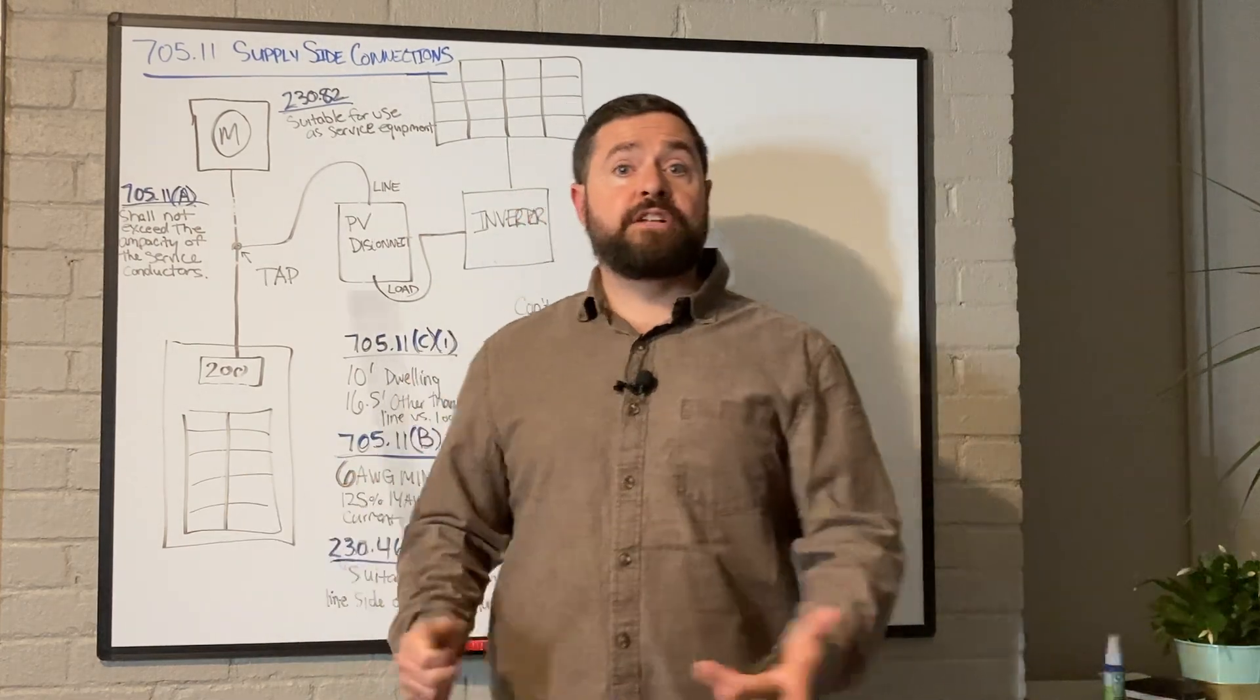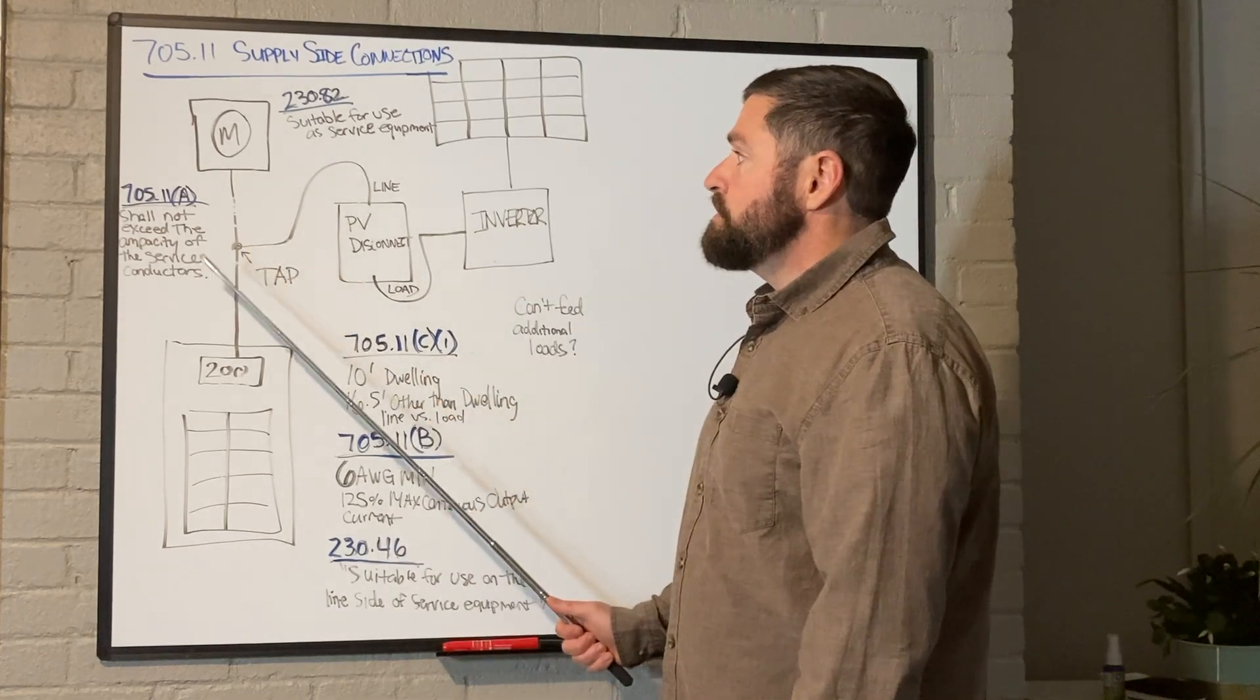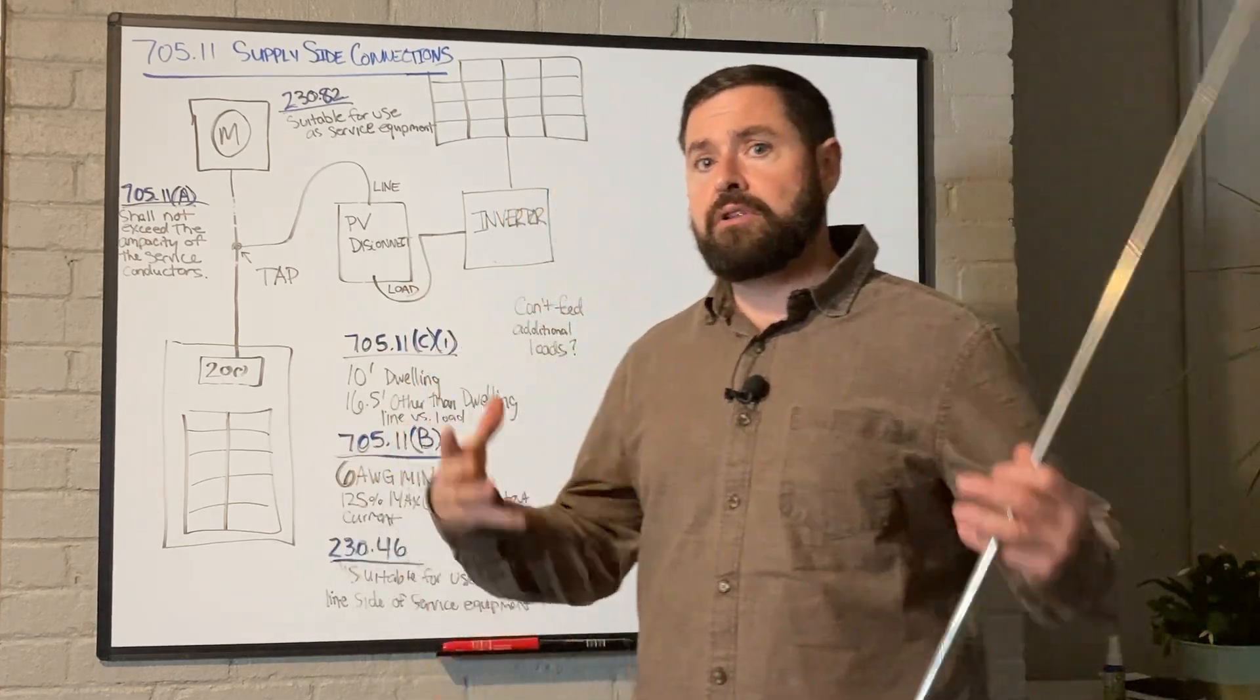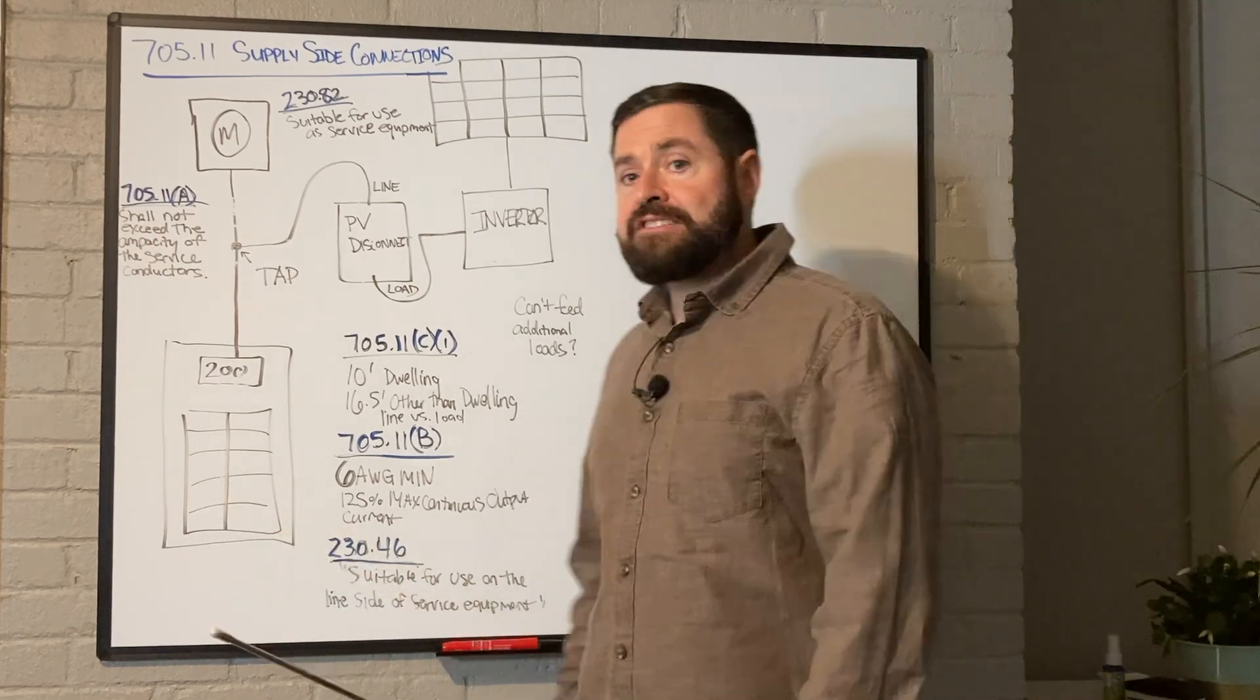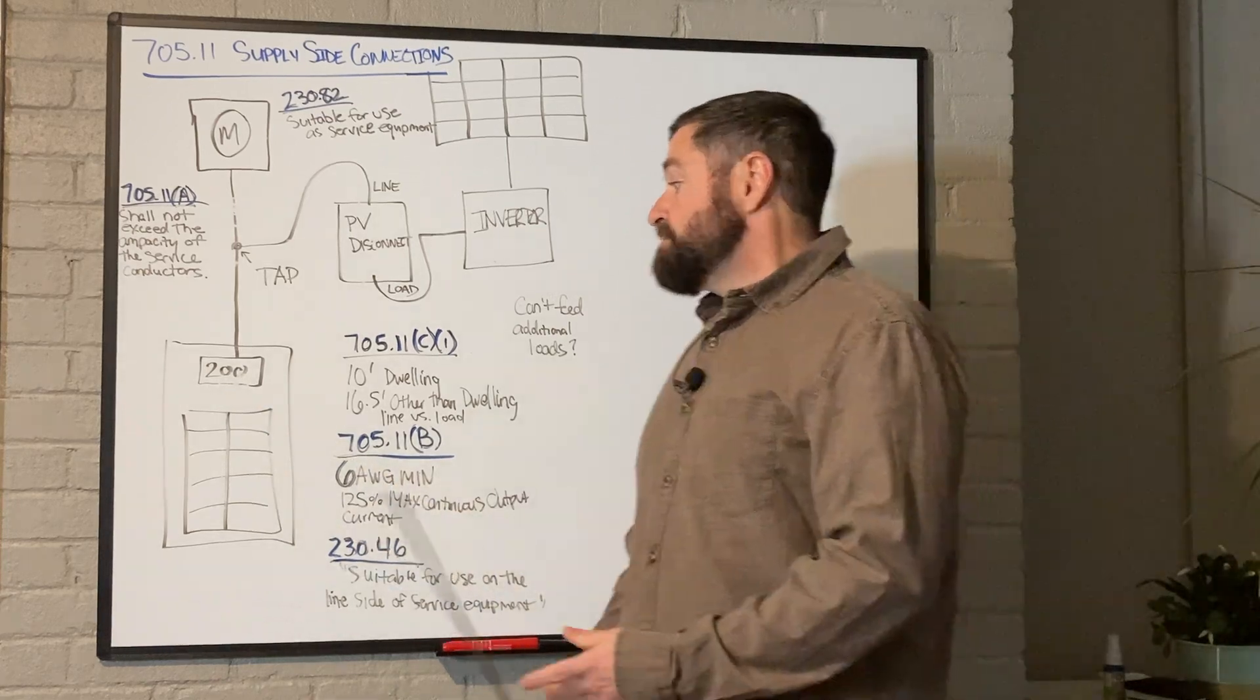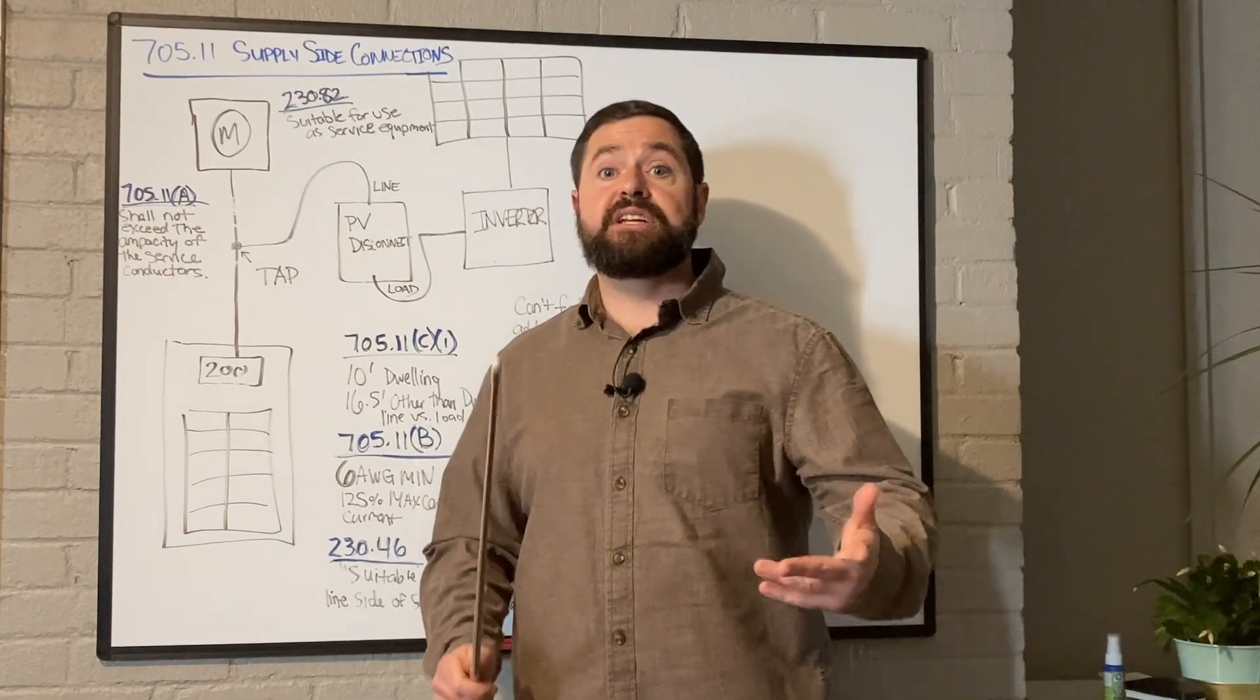So first of all, why would we even want to do a supply side connection? Well, because there's very few rules to the supply side connection. It's a really easy go-to when you have a large solar or storage system where you don't have to mess around with all the stringent requirements that are involved with connecting on the load side of the service equipment, specifically like the 120 percent rule or the solar back fed breaker rule, which you can see in one of my previous videos.